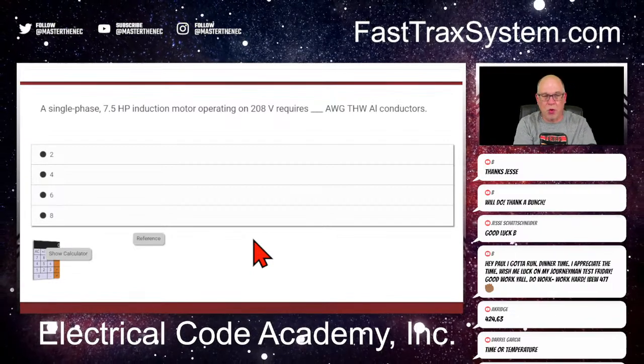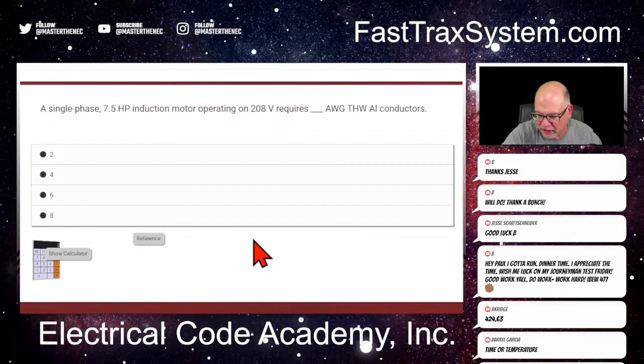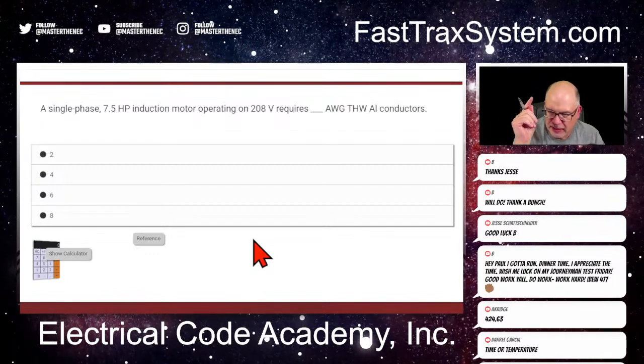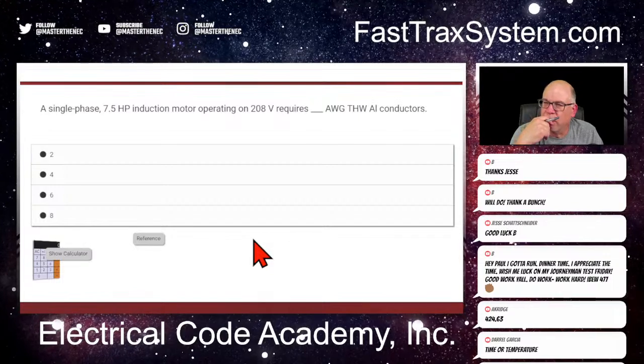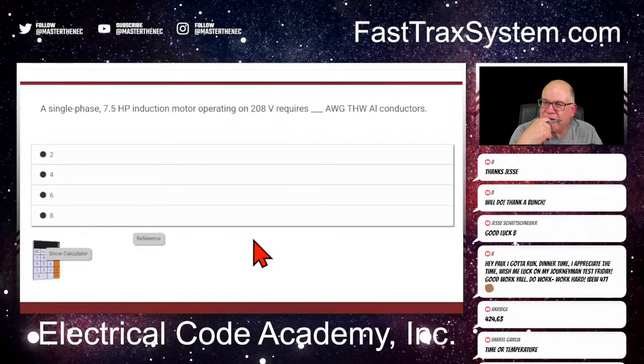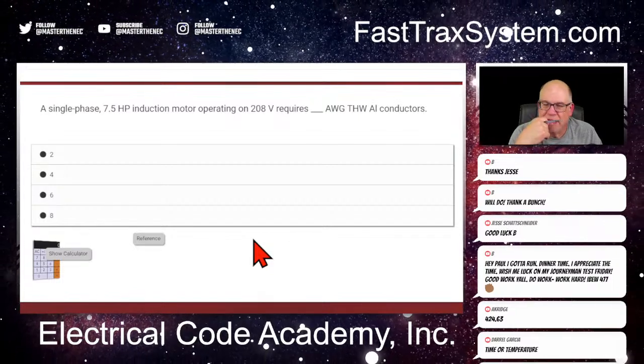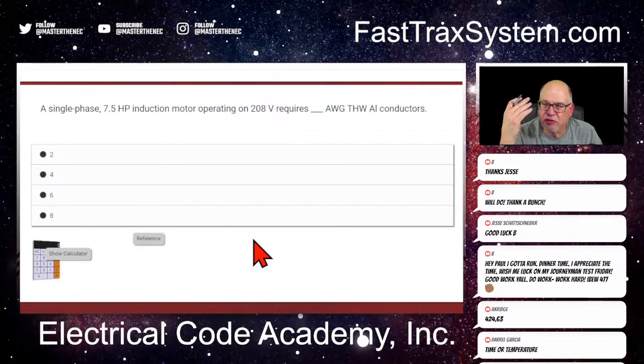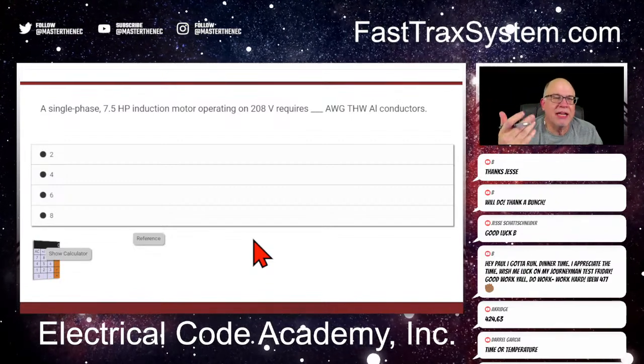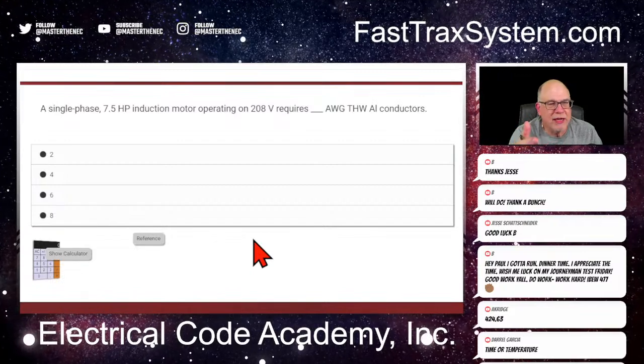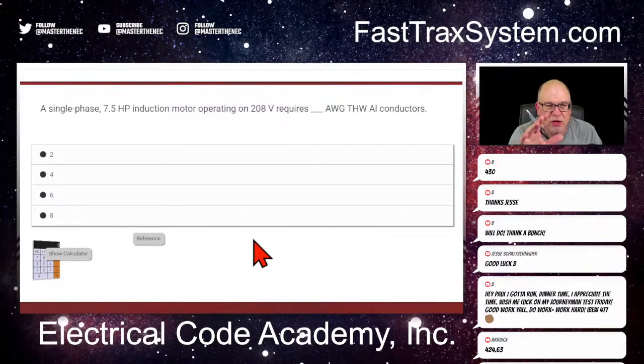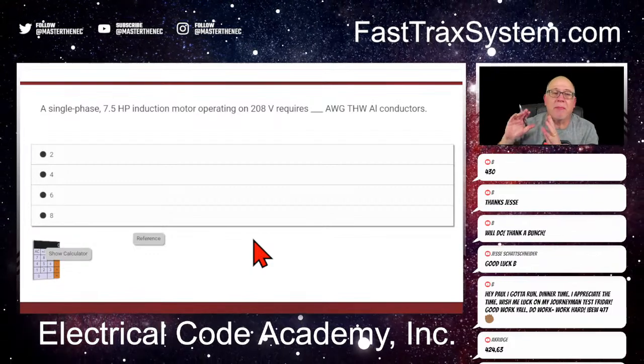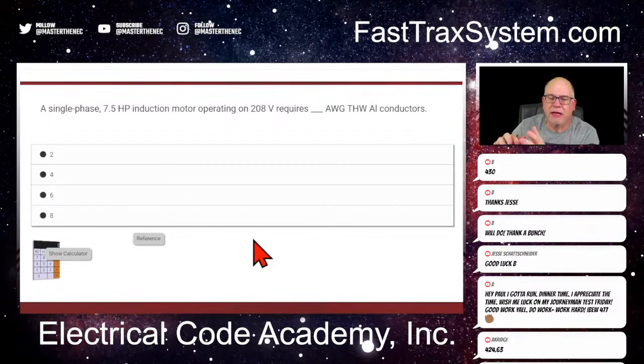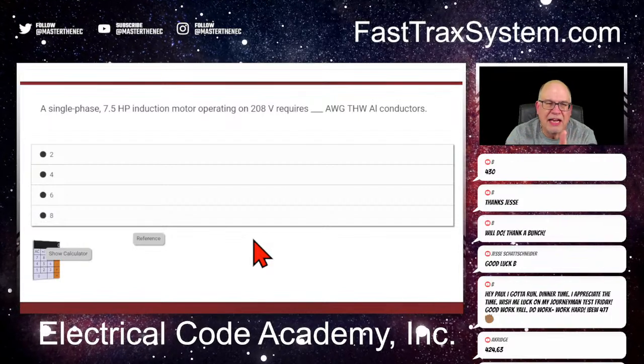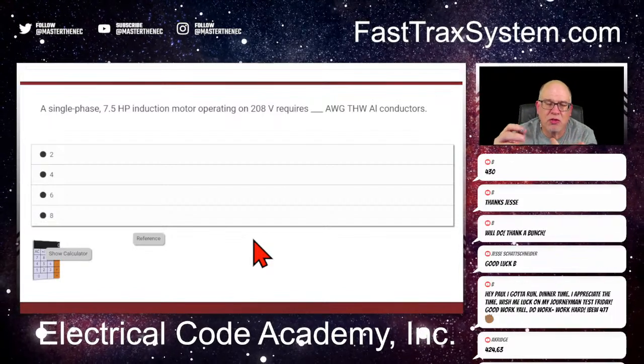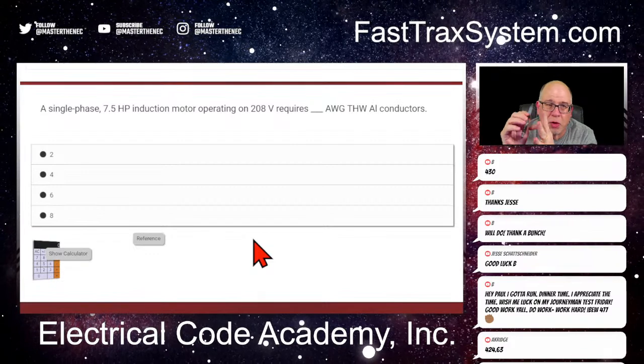Okay, so we got to do a little work here. The first thing we'll think about is that it's only going to benefit me to do anything if I know what the amps are. And so we're dealing with a motor, I got to know where to get amps. Y'all all know where to get amps, so you should know. There's 3 or 4 specific tables in the back of Article 430: 430.248, 249, 250. Those are the ones you use primarily for finding the FLC for motors.